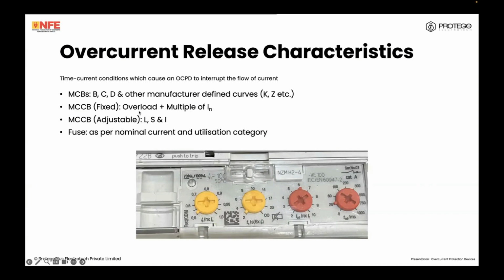L is the long time, which is to prevent tripping when there are starting currents or inductive loads that draw a great amount of current in the beginning. S is a short time tripping, which defines, if there is a breaker that has to wait to trip, how much time it will wait and what current it will wait for. And I is the instantaneous current, which is, if there's a certain amount of current, the breaker will trip without waiting. For a fuse, this is as per the normal current and the utilization category. So if it's a gM fuse to 60269, 10 amps, a certain fuse system, it'll have a certain defined tripping curve as per 60269. So there's nothing to change there.